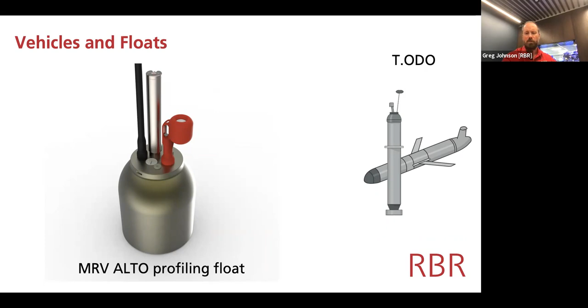Deployments on floats are also common. You'll notice that this one, which is on top of the MRV Alto float intended for the Argo program, the sensor appears to be longer than those pictures you've seen earlier, and that's correct. It's because we're following the TODO recommendation for having 20 centimeters of freeboard between the waterline and the oxygen sensor, so that when we're at the surface, we're able to make a surface air measurement to ensure that you can assess drift over the lifetime of the float, which might be 4 or 5 years.